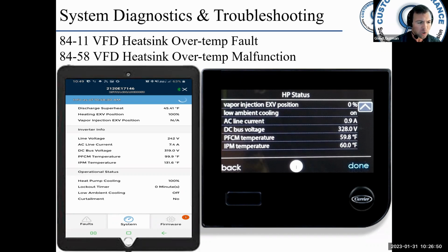Okay. Most likely the cause is restricted airflow over the heat sink, recirculation of condenser discharge air, could be high voltage issues, connections. Check the connections, especially on the reactors. Inadequate contact of power components with the heat sink, not allowing the intended heat transfer between components and the heat sink. So, again, you look at all those things. Really, you can see some of that stuff with your eyes. Is it recirculating air? Is it dirty? That sort of thing. Okay.